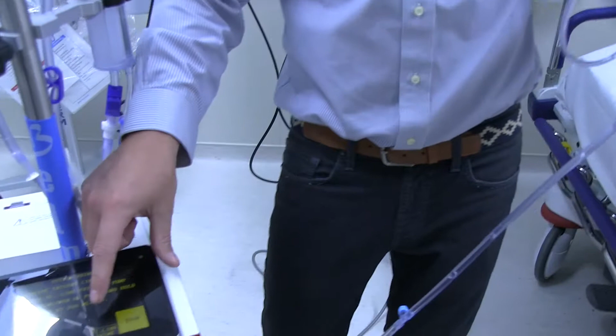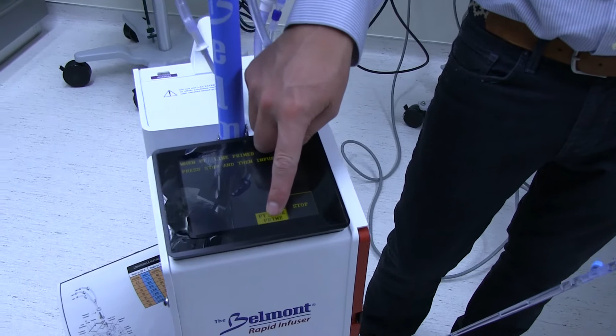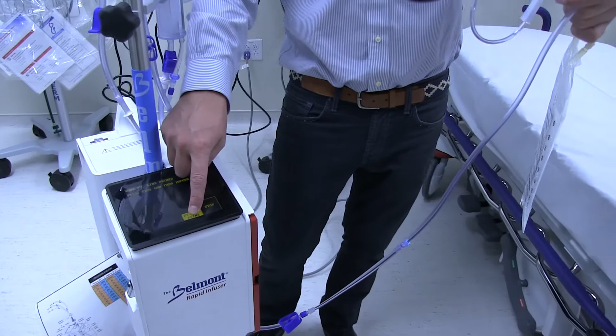You can press patient line prime once. It'll prime at 50 a minute. You can be doing something else, but if you're in a hurry, press and hold, and it'll prime the line out at 200 a minute. So you just do this until you're sure there's no air left in the line, and then when you're clear, hit stop, and it's a luer lock connection to the patient.